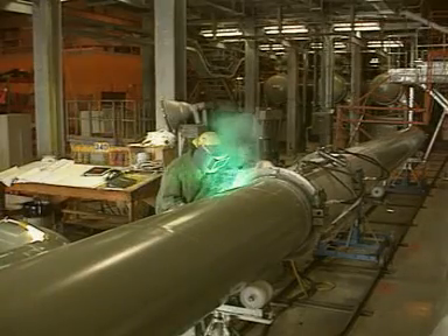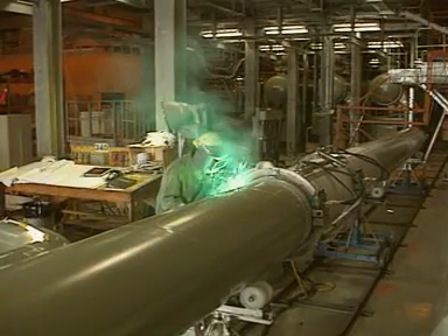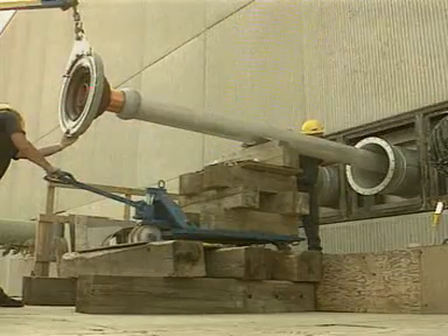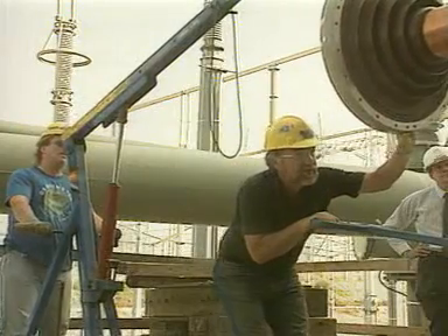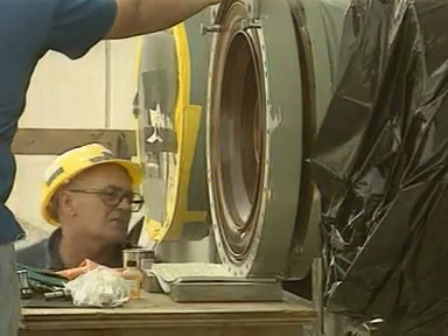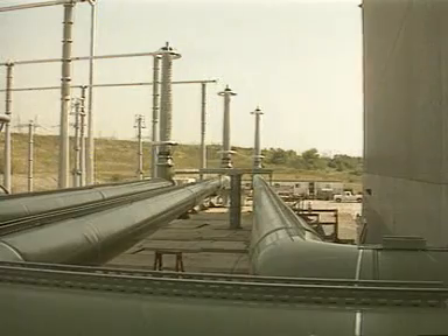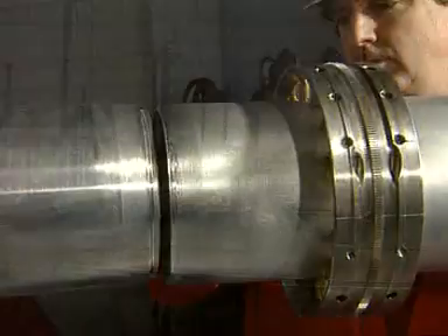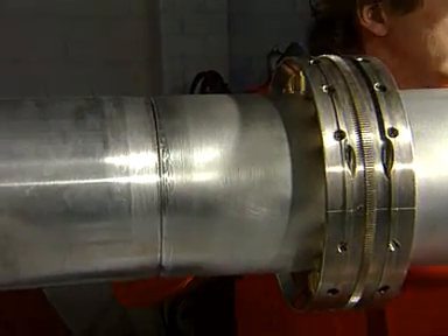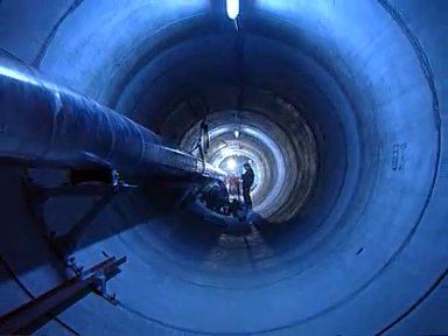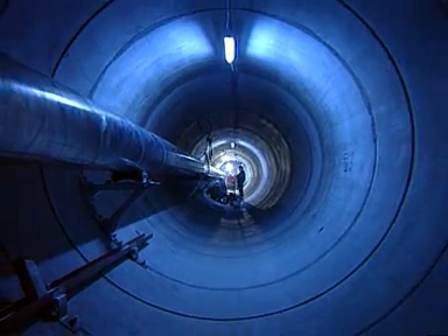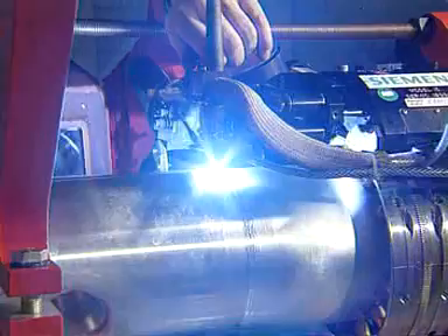The SF6 insulated tubular conductors are welded on site. A total of 3,000 meters of tubular conductor link the indoor switchgear to the extended overhead line. Innovative assembly and laying techniques now enable efficient use of gas-insulated tubular conductors as an alternative means of transmission, even over long distances.